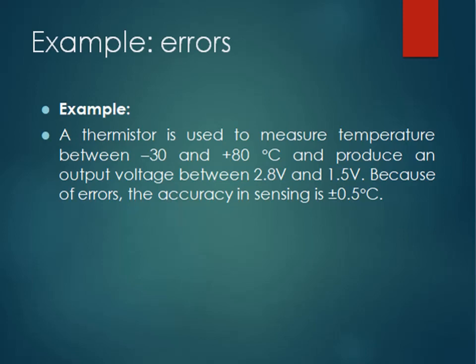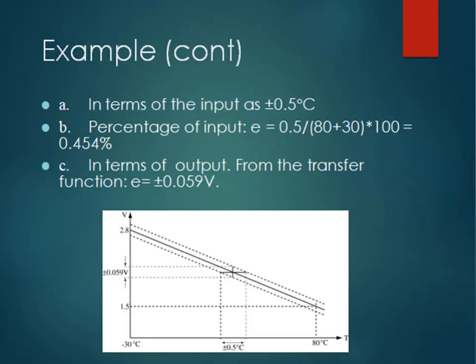Just take an example for error. A thermistor is used to measure the temperature between minus 30 and plus 80 degrees Celsius and produce an output voltage between 2.8 volt and 1.5 volt. Because of errors, the accuracy in sensing is plus minus 0.5 degrees Celsius.